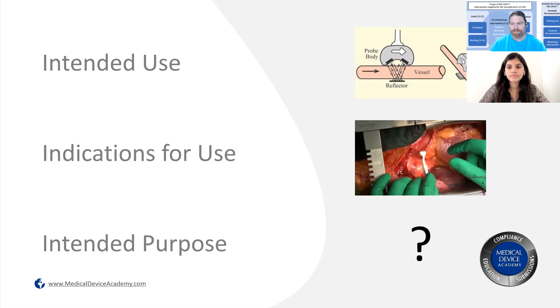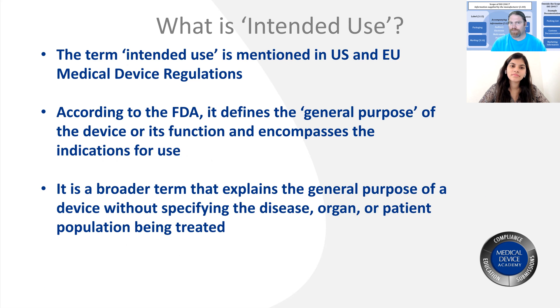So what's intended purpose? Let me cover the others first. The term intended use is mentioned in both US and European regulations — the new Medical Device Regulations, or MDR. It's a generic high-level term. According to the FDA, it's the general purpose of the device — a broad function, not something detailed. You don't have to put it in your labeling, and you're not actually required to submit something that says 'this is my intended use' in a 510k or CE marking submission. What they want in your labeling and submission is the indications for use.